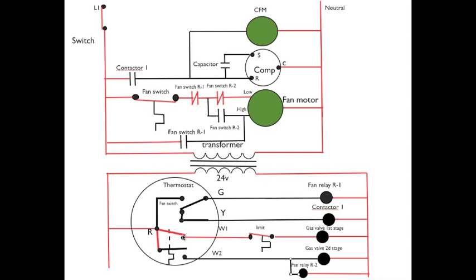So the first stage thermostat power passes through it, the normally closed limit energizes a gas valve in first stage. Fan switch closes as the heat exchanger warms, passes through the normally closed fan switch R1 and also through the normally closed fan switch R2 to energize the fan on low speed. Note this fan relay is not energized down here, so it does not change position.